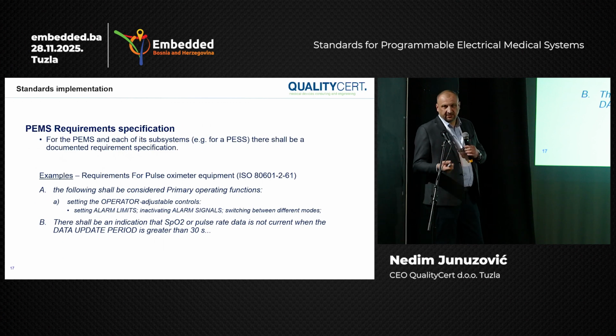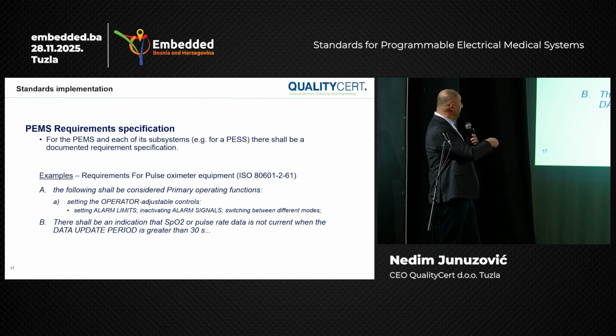Sometimes, of course, in startups, students and engineers who are getting into this work may not have had the opportunity to hear what the requirements are. I made two examples from the standard for pulse oximetry. It says the following shall be considered primary operating functions: settings, operator adjustable controls, settings alarm limits, inactivating alarm signals, and switching between different modes.